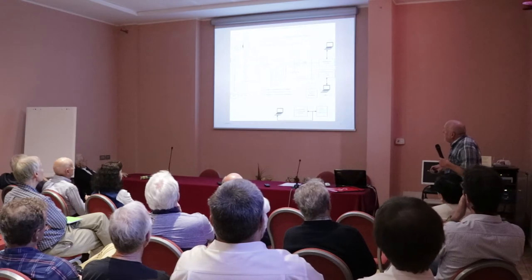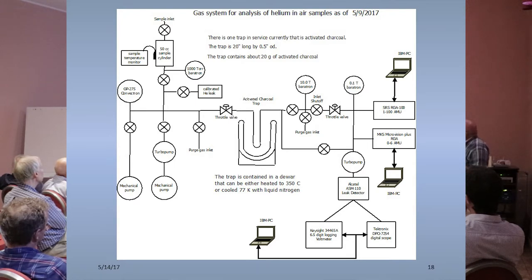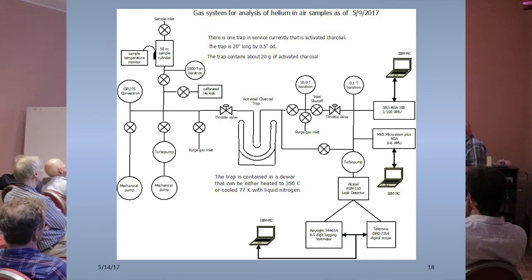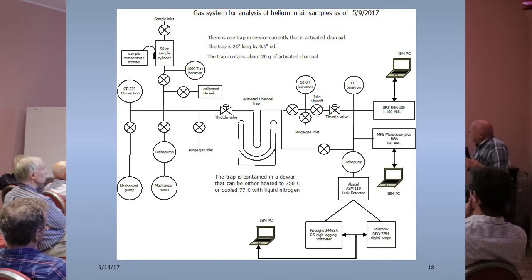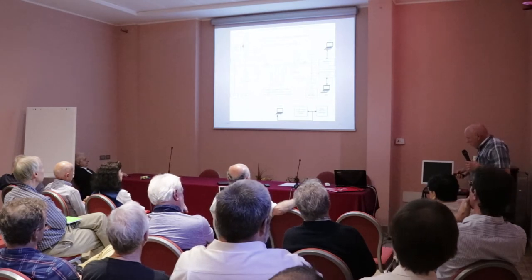We now have the final configuration of the system we're currently operating with. The only difference from the previous one is that we've added a calibrated leak. We can make it put helium into the system at a constant rate at the same point that our regular samples go in, which has two effects: we can verify the leak detector is operating properly by tuning it for mass 4 and sensitivity, and it provides a method of doing calibration. We've eliminated using the digital scope and do all the data with the six-and-a-half-digit voltmeter.